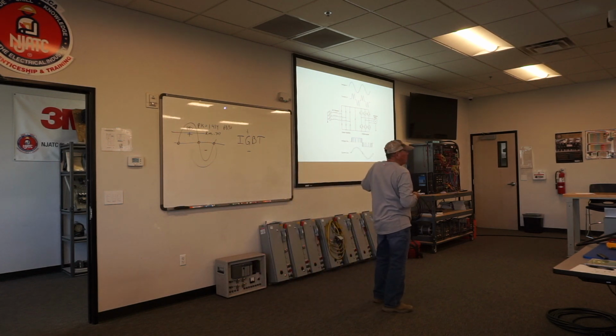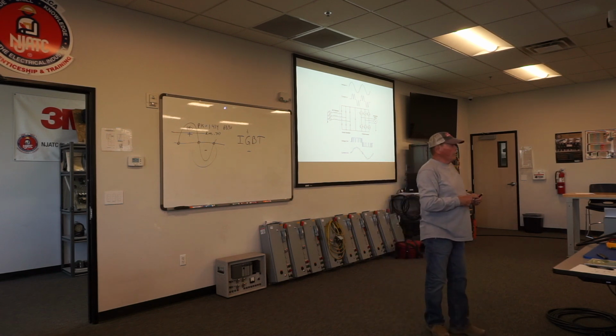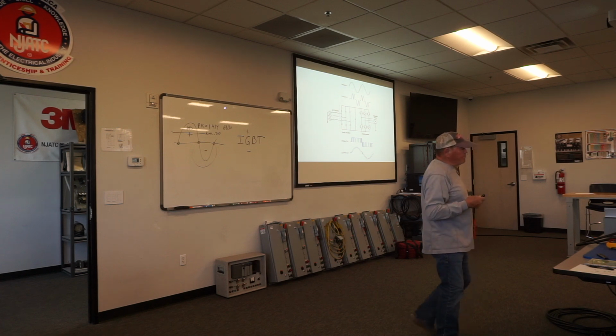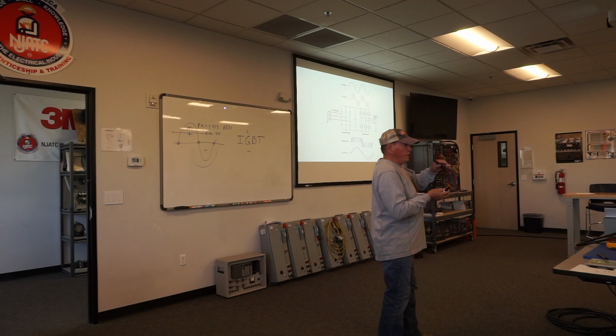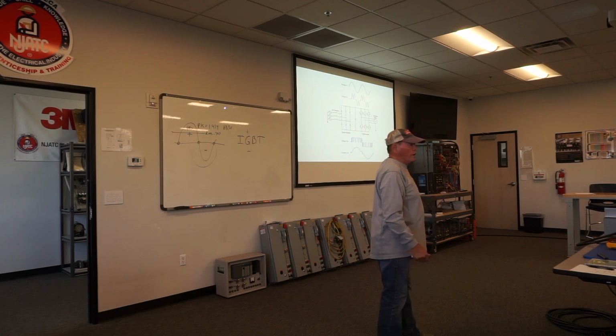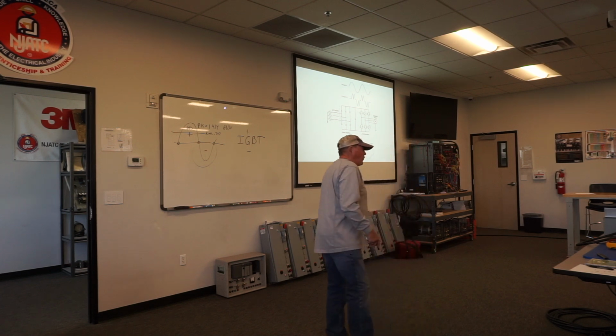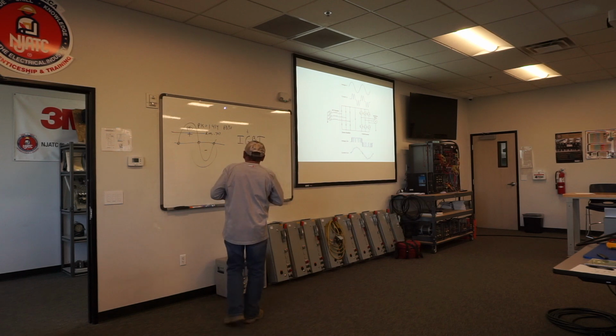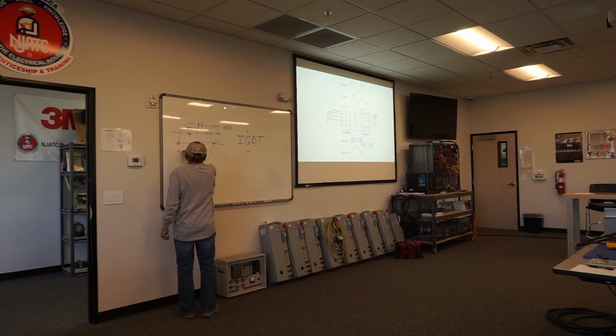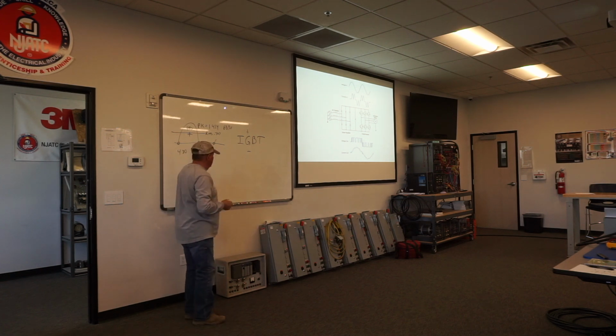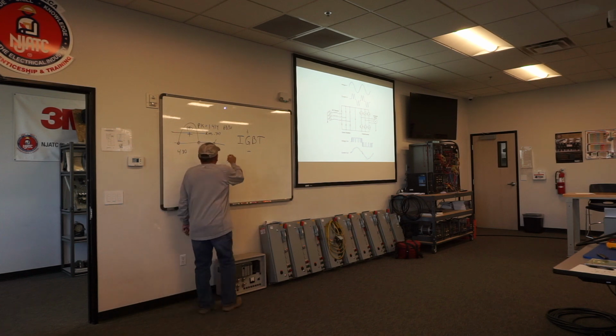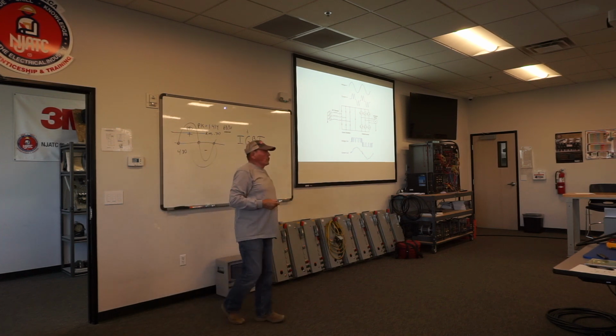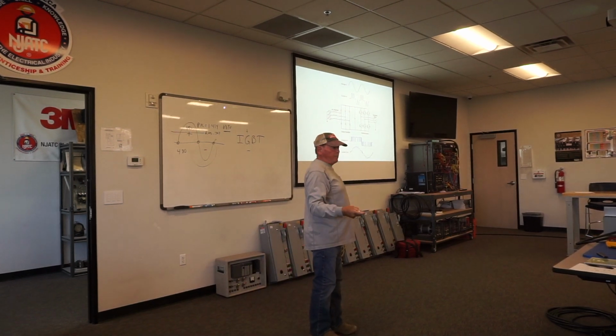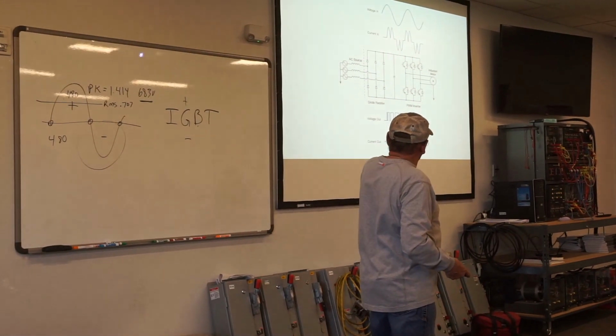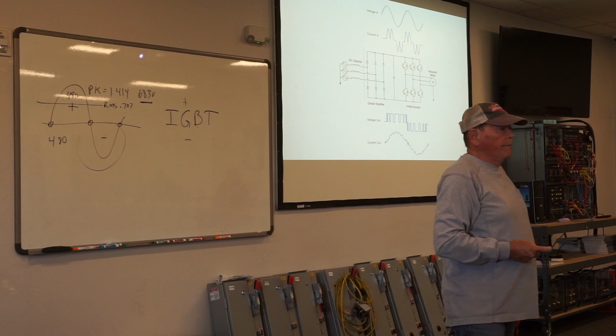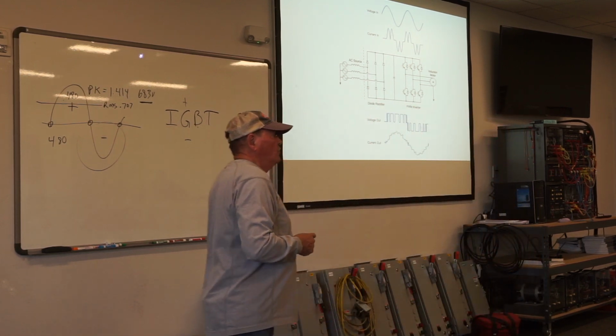So, do I have the value I need to provide 600 volts for that DC bus? It has to be plus 600 volts. 600 to 650, depending on the drive, but 600 or greater on that DC bus. Therefore, this 480 volts cannot be less than some value, or I do not create this value. So low voltage can cause voltage dips, and can cause that DC bus to not reach its maximum.